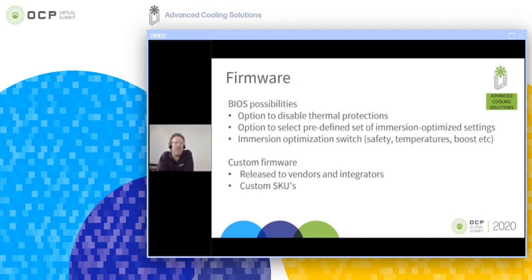And finally, there's the firmware. So when looking at BIOS possibilities, one of the things that could be considered, especially when designing IT equipment for both air deployments and liquid deployments, is to allow an end user, an integrator, or an immersion technology vendor access to certain options to disable thermal protections, depending on the type of immersion technology. There's, for example, an option to select a predefined set of immersion optimized settings, like what kind of intake temperature would be engaging, what kind of safety protocols.